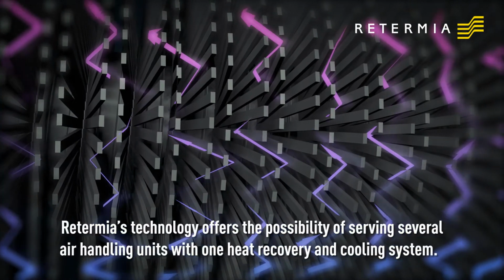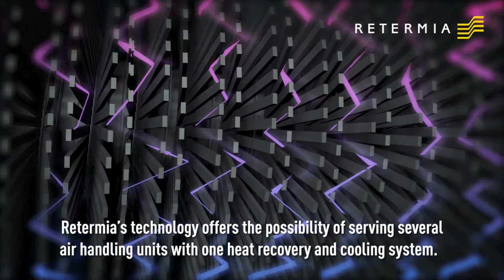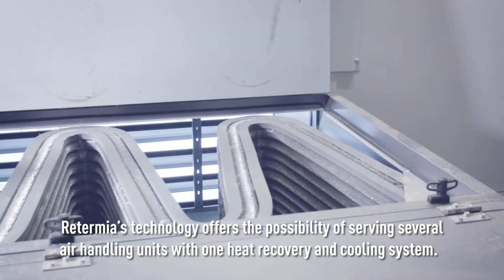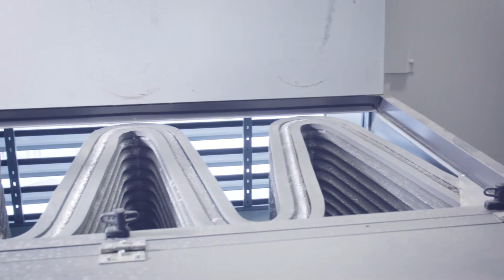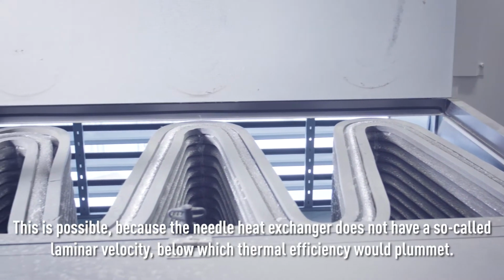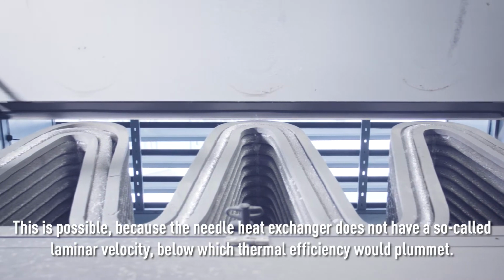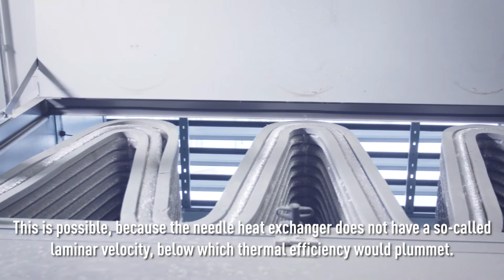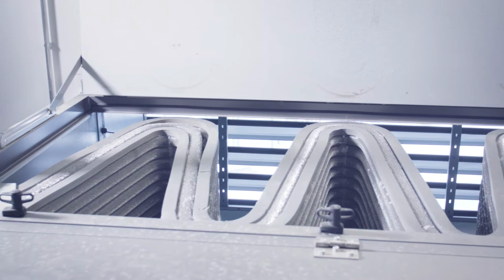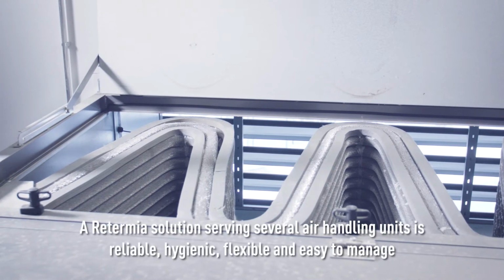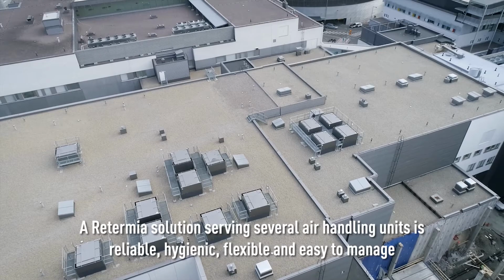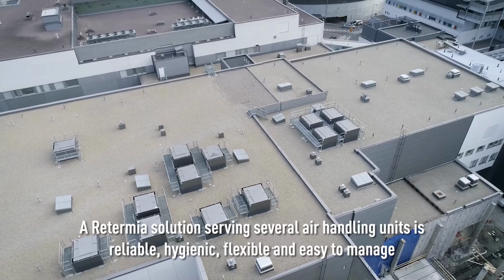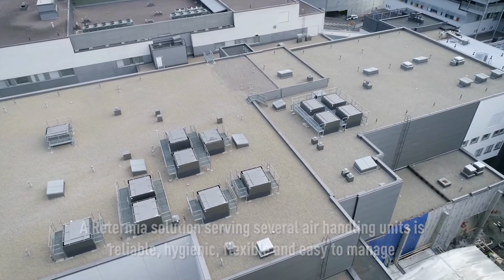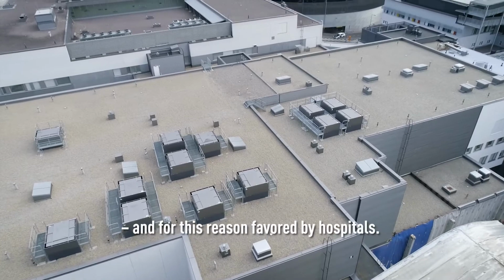Retermia's technology offers the possibility of serving several air handling units with one heat recovery and cooling system. This is possible because the needle heat exchanger does not have a so-called laminar velocity, below which thermal efficiency would plummet. A Retermia solution serving several air handling units is reliable, hygienic, flexible, and easy to manage, and for this reason favored by hospitals.